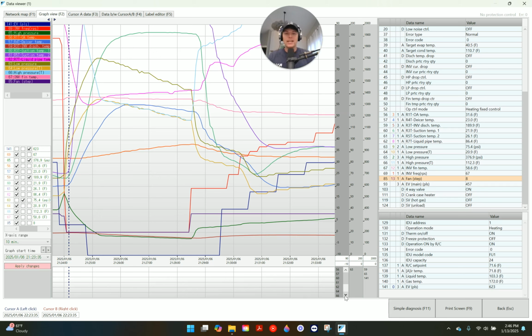And now once I get at least 3 to 5 things that can give me a good picture, I look at it throughout the entire data set from front to back. Start here and work my way nice and slowly through it and see if I find anything crazy, right? 280 degree discharge temp. Well, that's a big problem. Maybe I should look at that a little bit more closely. Why is that? What is my suction superheat? Is it getting enough vapor? What is my discharge superheat? Is there enough oil in the compressor? Things that I cover in other videos.